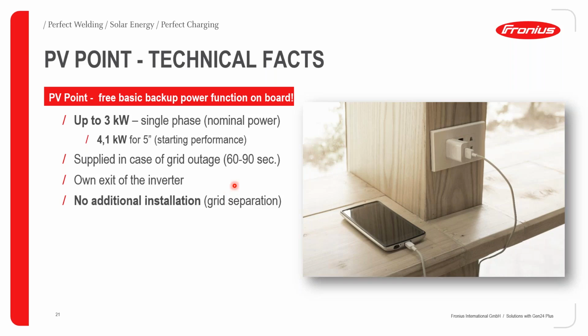The PV point will only be supplied in the case of grid outage, okay? So when the grid goes down, our GEN24 Plus will also go down, okay? The reason for this is that we always do checks, and we do the low voltage ride-through checks. And because we have so many country setups on our inverter, we have to make sure that we do the specific country checks to make sure that it's safe to go offline, okay? And also when we come back online, we'll always do our tests to make sure that it's safe to come back online, okay? This is the very reason for our shutdown time of about 60 to 90 seconds, after which we will come back online again. And after that period, we will then provide you with an output of 3 kilowatts single phase on the PV point, as long as you have PV power available.